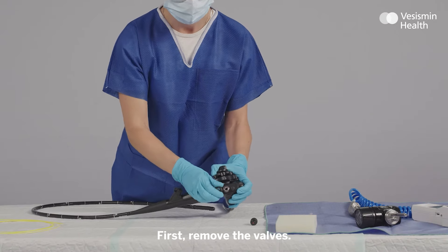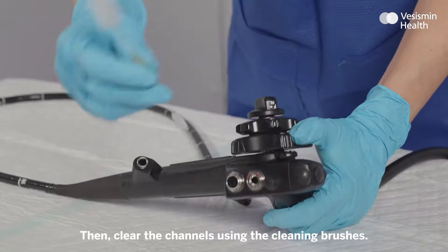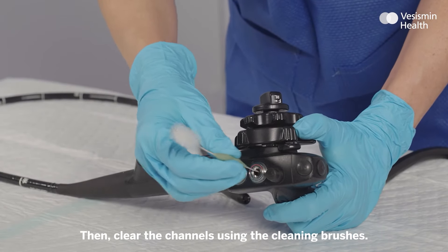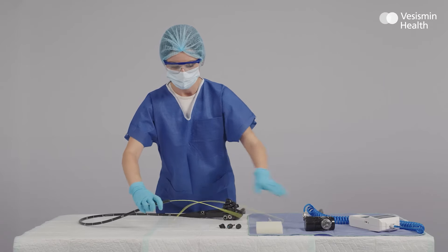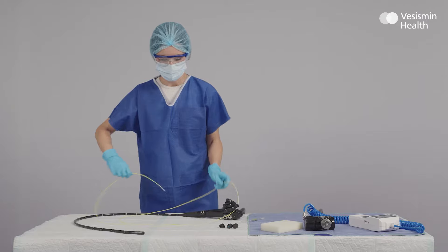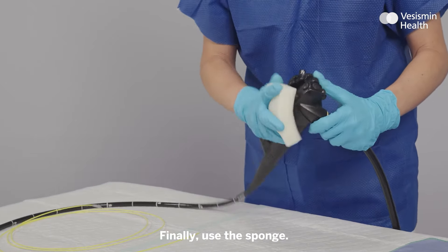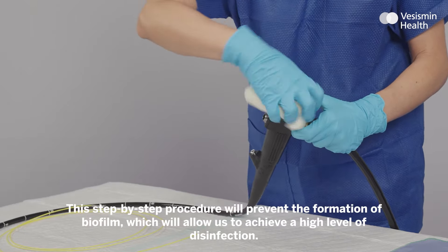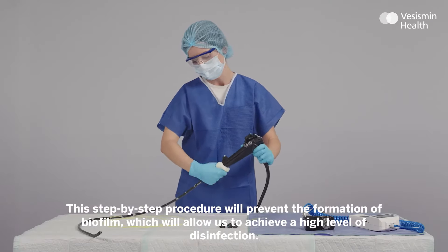First remove the valves. Then clear the channels using the cleaning brushes. Finally, use the sponge. This step-by-step procedure will prevent the formation of biofilm, which will allow us to achieve a high level of disinfection.